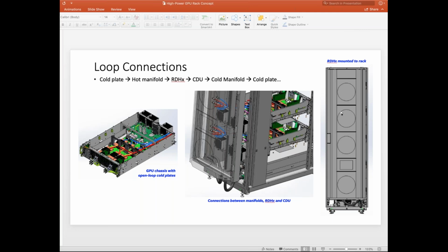And we haven't really defined where the manifold and where the fans are located. Right now we put the fans in the IT, but we can also discuss whether the fan goes into the rear heat exchanger or stays in the IT space, and where the manifold, the loop, the pipe and all that detail needs to be defined in the specification. We'd like to have community help. I'm requesting the community's help in defining these specifications.